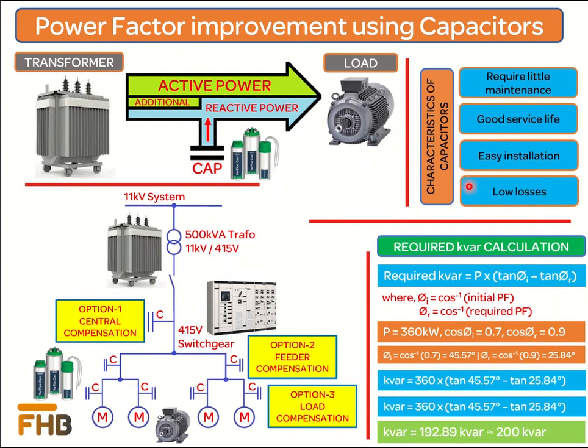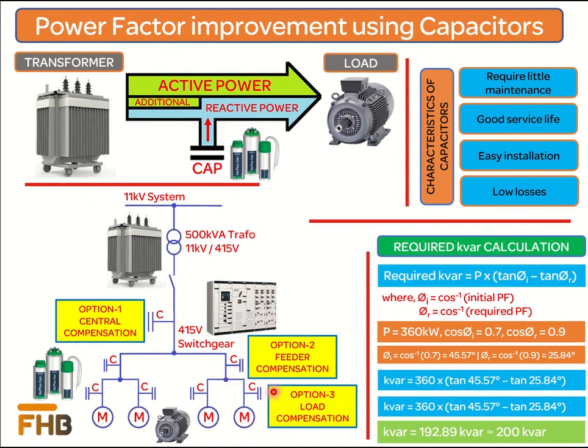The next phase is to determine where to install capacitor banks for power factor improvement. There are three possibilities. First is central compensation, where capacitor banks are connected after the secondary terminal of the distribution transformer to provide reactive power to the entire connected load — commonly used with continuous load factors. Second is to connect capacitor banks on individual feeders for varying load factors. Third is to connect capacitor banks at the load terminal, used for large industrial motors, providing reactive power exactly where it is needed.